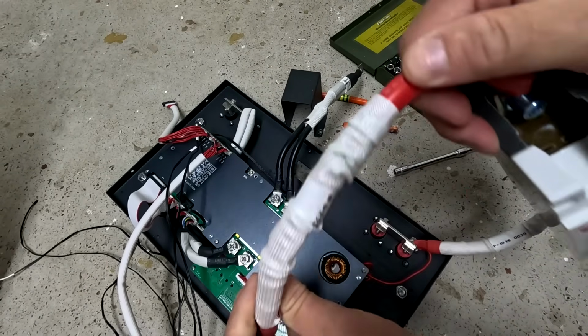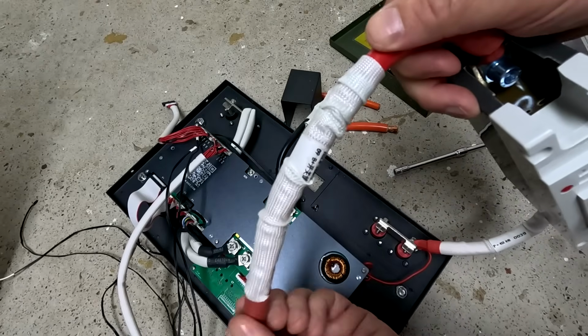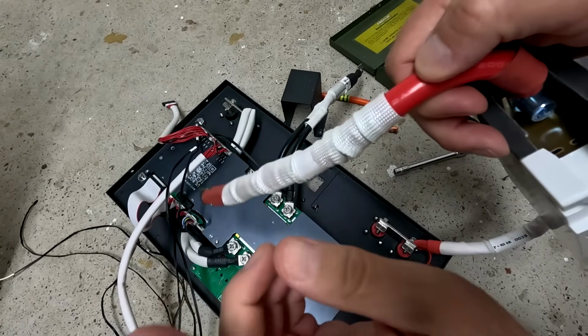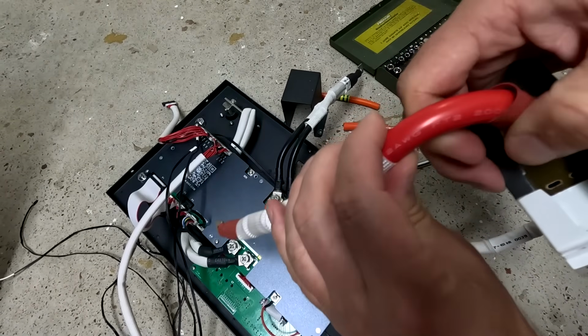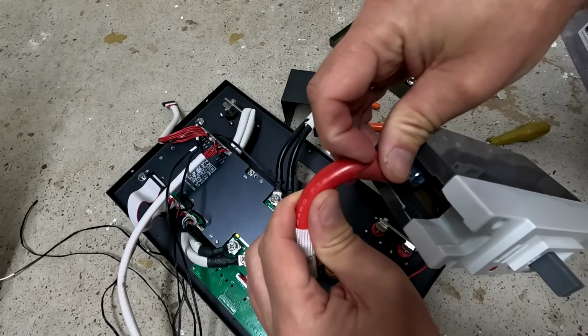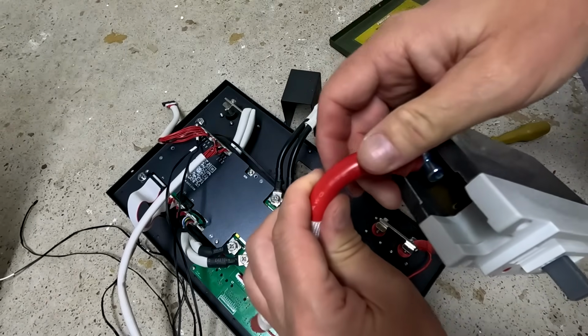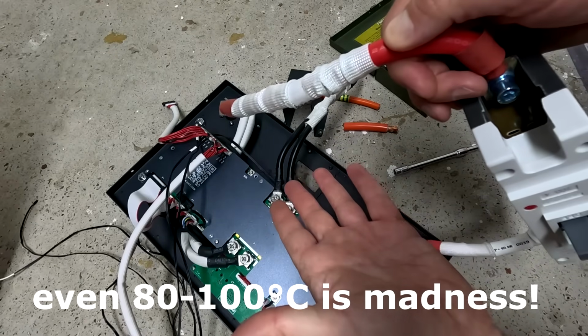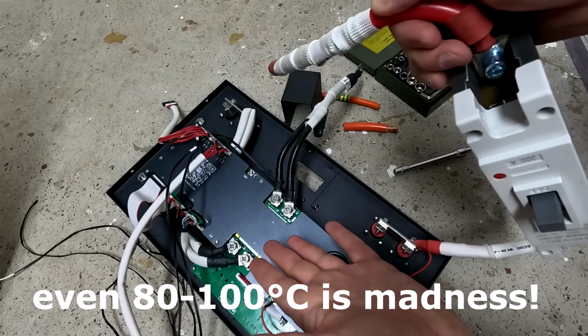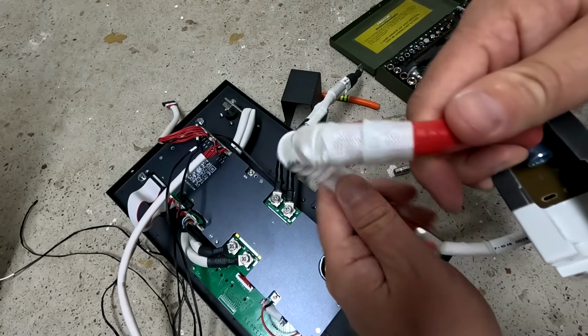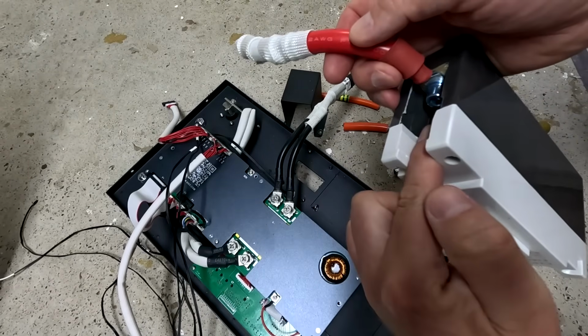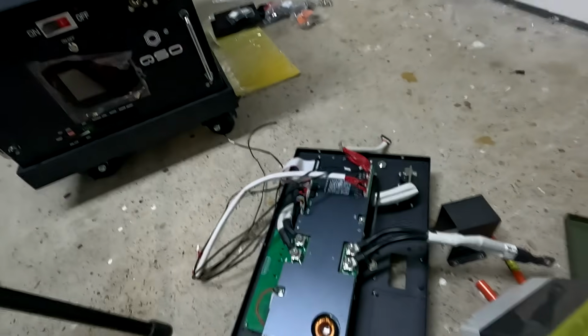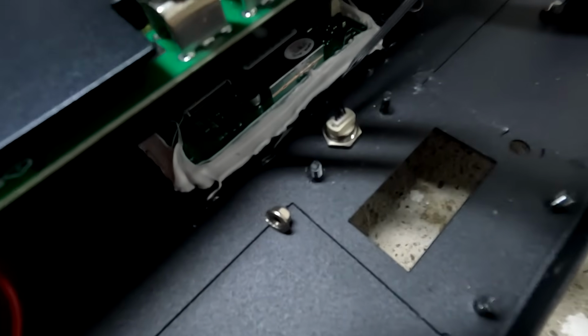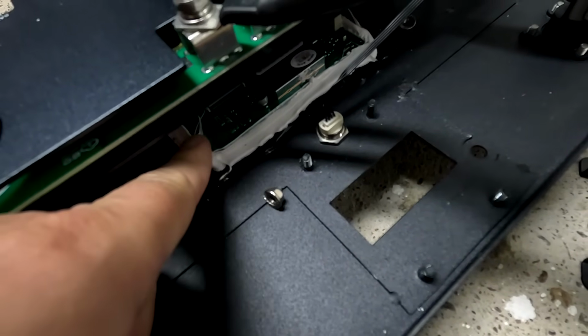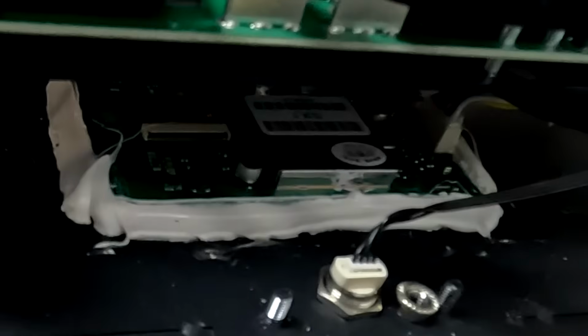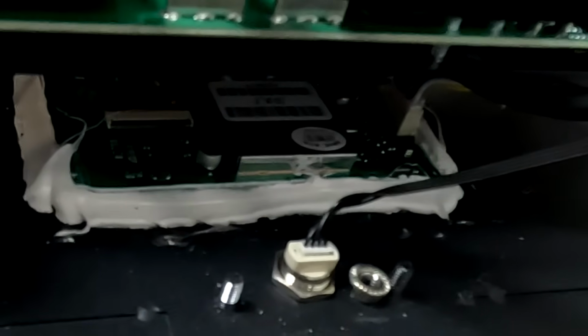Yes, these are highly flexible silicone cables. They can carry a bit more current, but under the sacrifice of heat. Yeah, they've got a heat rating, you can see it here, of 200 degrees Celsius. Do you want to drive these cables for 200 degrees inside the battery box? Probably not. So I think these cables are too thin for this circuit breaker. Whoa, whoa, whoa, whoa, whoa, what do I see here? Someone was really generous with, yeah, look at this. This is all just glued in with silicone.